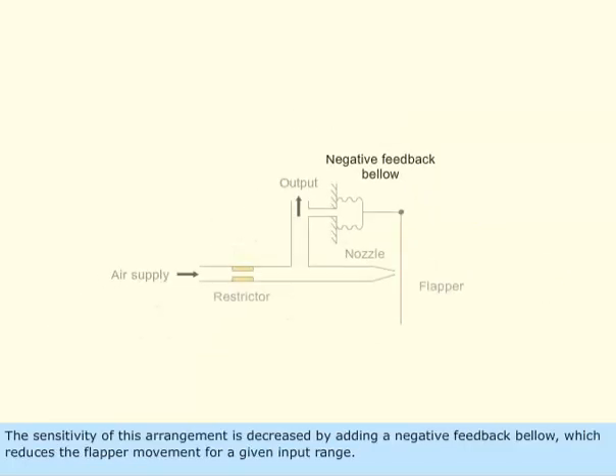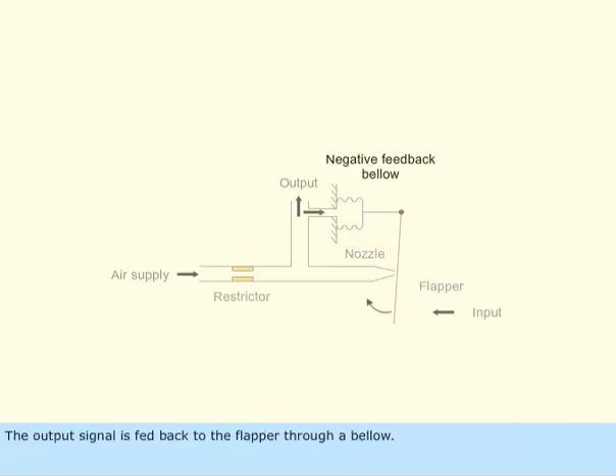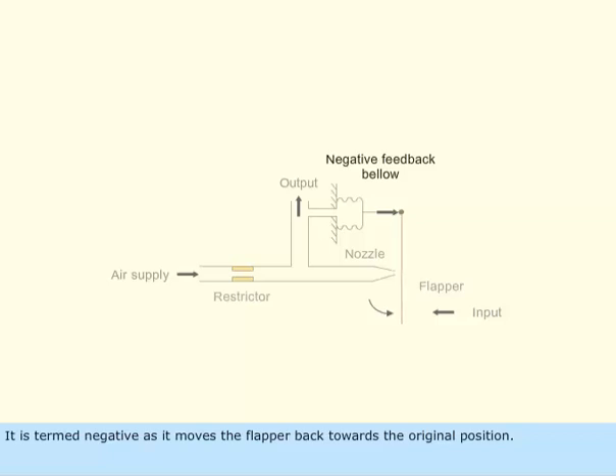The sensitivity of this arrangement is decreased by adding a negative feedback bellow, which reduces the flapper movement for a given input range. The output signal is fed back to the flapper through a bellow. It is termed negative as it moves the flapper back towards the original position.